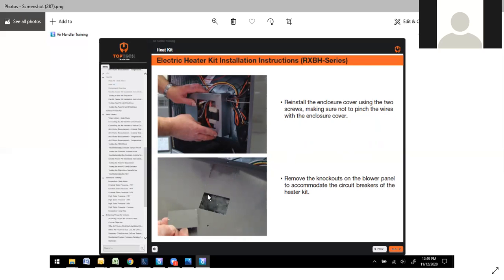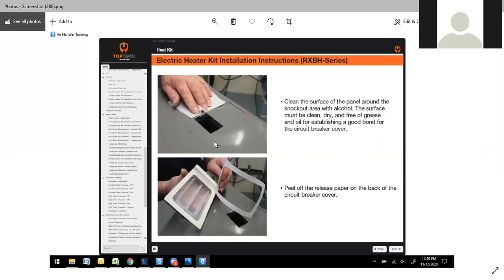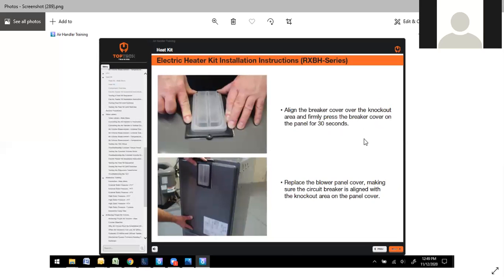At that point, you want to remove the knockouts, the amount of knockouts that you need on the blower panel to accommodate the number of circuit breakers that pertains to your heat kit. Clean the surface around that. The surface must be clean and dry, free of grease and oil. And it actually comes with this nice little cover right here. So peel off the release paper on the back, and then you can install your breaker cover. That'll keep people from actually getting to the breaker with their bare hands. Align the breaker cover over the knockout, press firmly for 30 seconds, and it should be stable. At that point, you can replace the blower panel, making sure the circuit breaker is aligned with the knockout on the panel cover. Those actually aren't very difficult. You can usually install those kits rather simply.